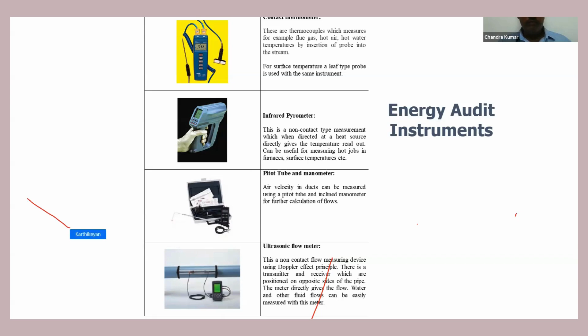This is a very quick way of measuring the water flow across a pipe. Generally, this has been used to get the pump efficiency. To know the pump efficiency, on the input side of the motor we can use a power analyzer to get the input side electricity, and for the output side, you should know the pump output. For that we use an ultrasonic flow meter for measuring the flow of the pump.